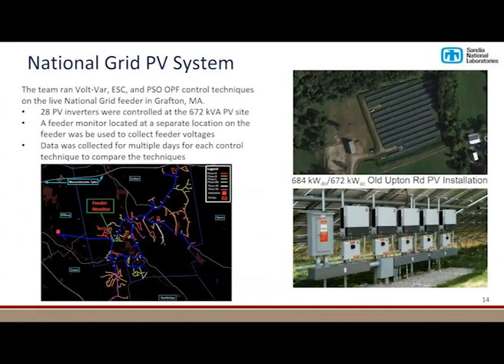Okay, so based on all that, we had some confidence that our controllers were working, and we were ready to go to the actual field demonstration. For this, we were communicating to the Old Upton Road PV site that the National Grid owns. We had another point on the feeder, shown in the lower left, where we had a feeder monitor, and we could pull currents and voltages off of that measurement point.